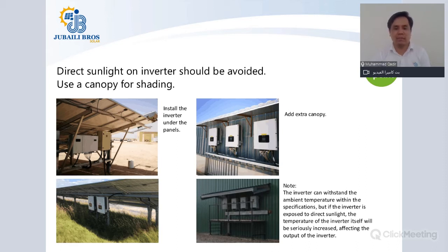That way the inverter can withstand the ambient temperature within the specifications, but an inverter exposed to direct sunlight will have an increased cabinet temperature, which will affect and derate the output. Although the data sheet mentions that the inverter can bear around minus 25 to 60 degrees Celsius, there is also a derating factor involved with the temperature change. So the best way of installing your solar inverter outdoors is to have a shade when it is exposed to the sunlight.